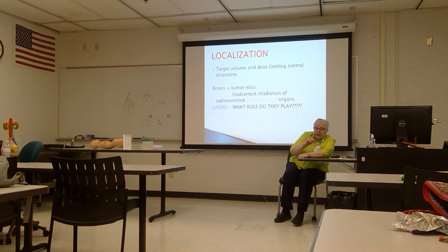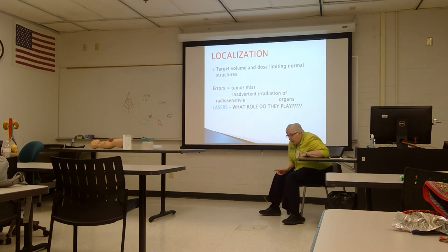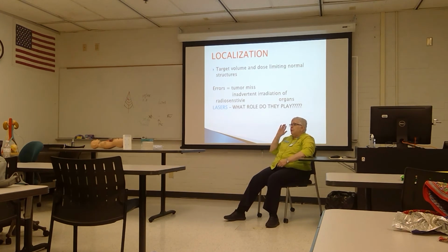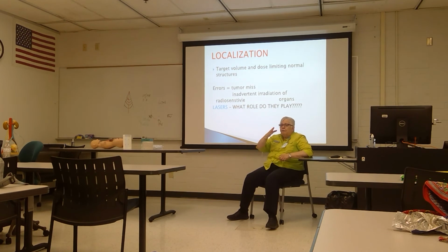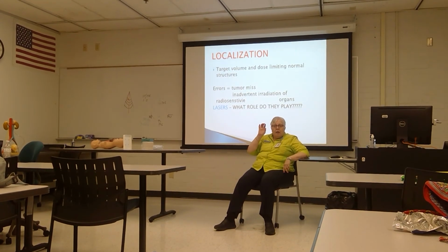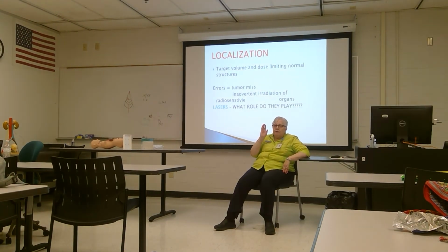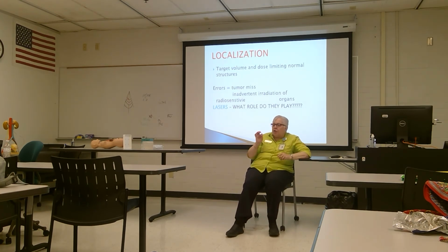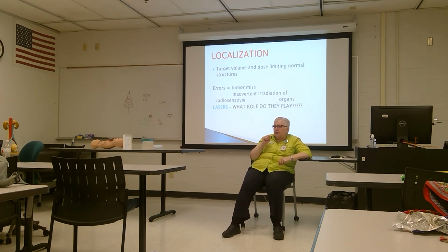We got talking, that's right, because depending on what you use, you either set up to the tattoos and move to the treatment marks, or we set up to the treatment marks. That's all very well if the lasers are accurate. They should be checked daily, the lasers.